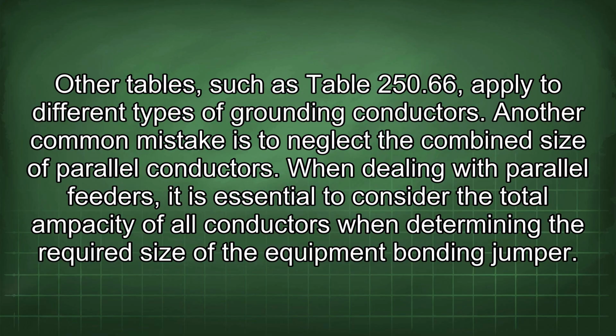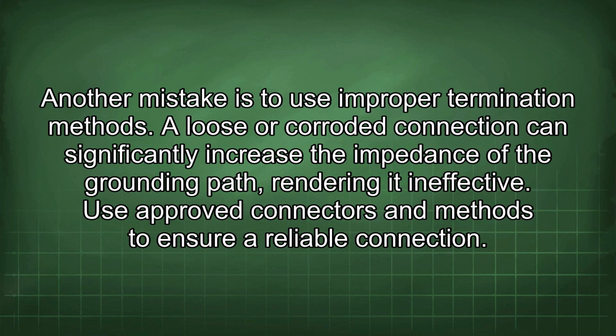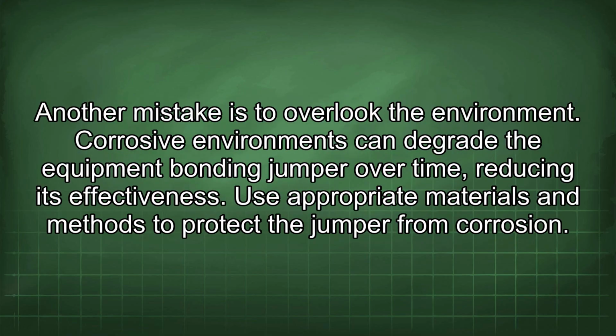Another common mistake is to neglect the combined size of parallel conductors. When dealing with parallel feeders, it is essential to consider the total ampacity of all conductors when determining the required size of the equipment bonding jumper. Another mistake is to use improper termination methods. A loose or corroded connection can significantly increase the impedance of the grounding path, rendering it ineffective. Use approved connectors and methods to ensure a reliable connection. Another mistake is to overlook the environment. Corrosive environments can degrade the equipment bonding jumper over time, reducing its effectiveness. Use appropriate materials and methods to protect the jumper from corrosion.